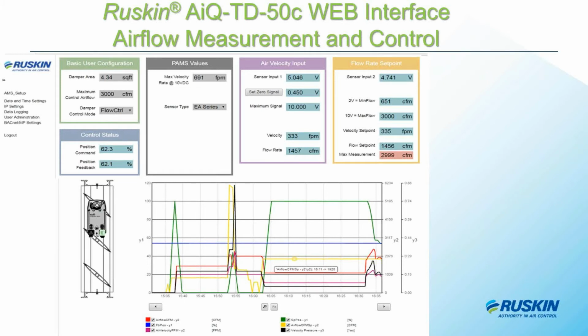either version of BACnet. Those of you that were at our booth this year in Chicago at the ASHRAE show got to see this setup screen in person. The actuator has a web server built into it. And so you access the web server by simply plugging an Ethernet cable directly into the actuator, and then with any laptop using Google Chrome, you can log on to the server. And the installing contractor uses this setup screen to configure the air measurement station for the installed system and to configure the automation system to talk to this particular actuator. So you're able to set the baud rate, device instance, and MAC address, all configurable on the actuator, and that's done in the field.